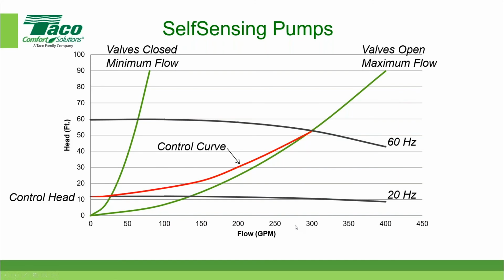Yes, it is. Okay. So when we talk about a control curve, we have to know 2 points in order for the software to find out where the curve needs to start and finish. One of those data points is very easy because all of us know that we are selecting the pump at the design operating point. In this case, it happens to be 300 gallons per minute at 53 feet of head. However, we also need to know where it intersects the y-axis, or the vertical axis, which we call the control head.